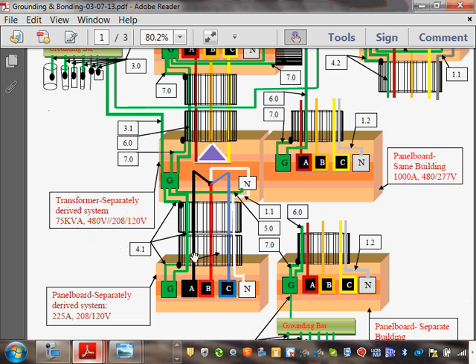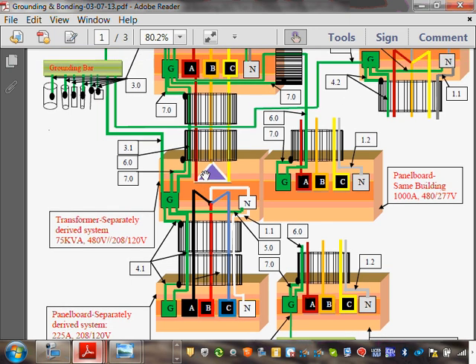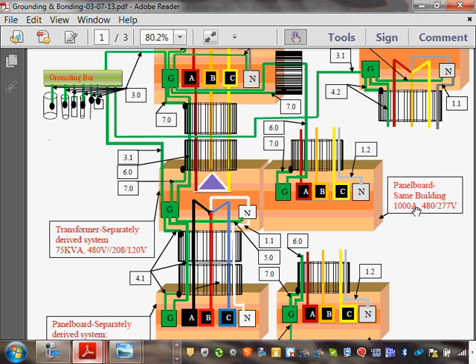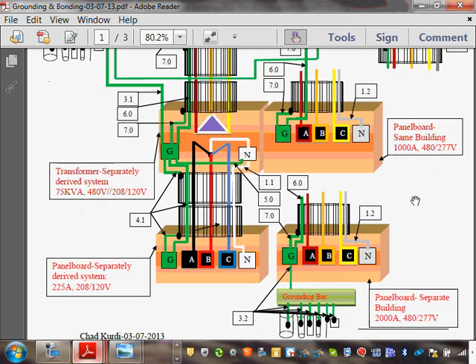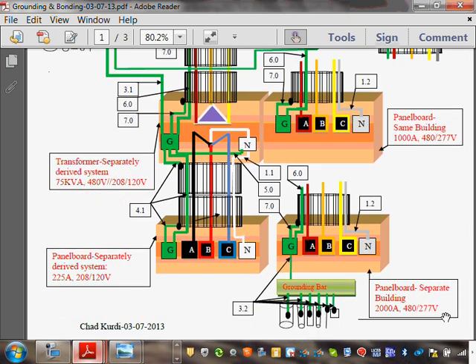Every respected building that has a 480/277 system will have these scenarios in it, right? So I have a transformer that feeds a 208/120 panel. It happens to be 225, commonly used. So that's feeder 1 coming out of the service. Feeder 2 is 1,000 amp. For all practical purposes, that could be your 60 amp going to your detached garage in the same building. Could be a 60 amp, so don't let the 1,000 amp scare you. This is the same building, still a 480/277. Then a third feeder is going to a separate building.